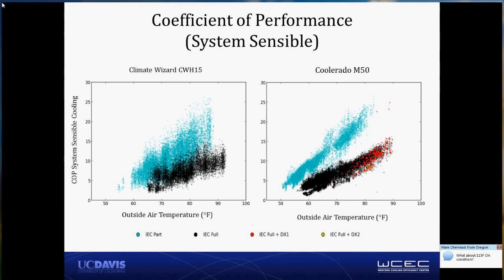When you look at a big box store, there's some rooftop units that never run. Literally, very, very few hours of the year will their compressors ever turn on. They may even be running their fans continuously to provide ventilation to the space, but somehow the load in that zone is carried by another unit, or the load in that zone is very low because there's very few people or very few lights or equipment or what have you. So we can't make any conclusions from our evaluation here about any differences in the capability for these things to offset compressor runtime hours, because they're serving different spaces even though they're controlled in the exact same way.